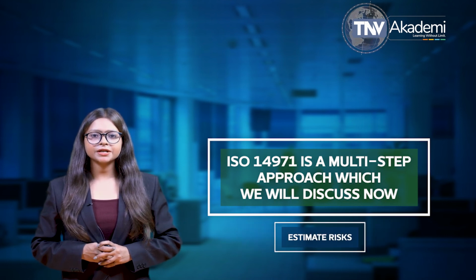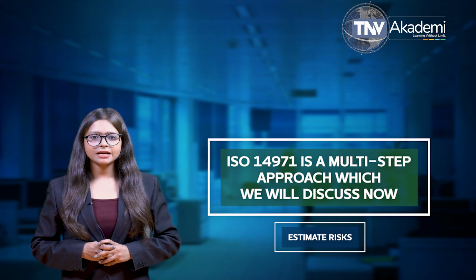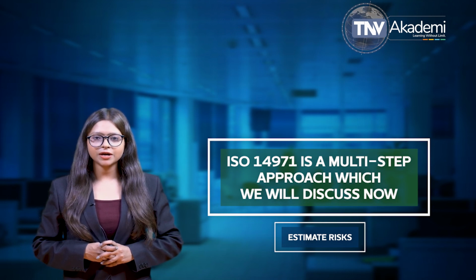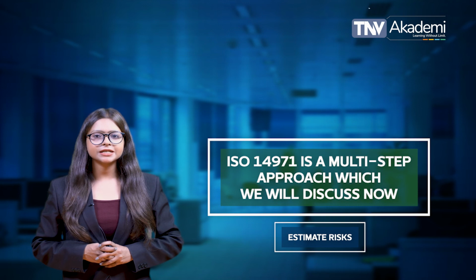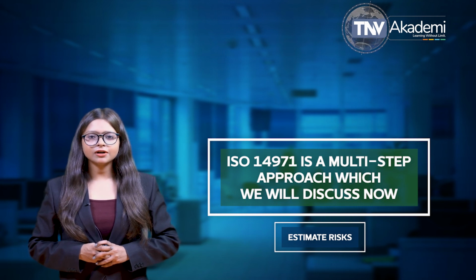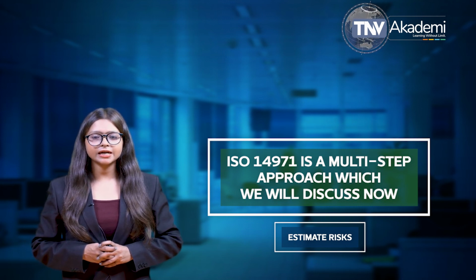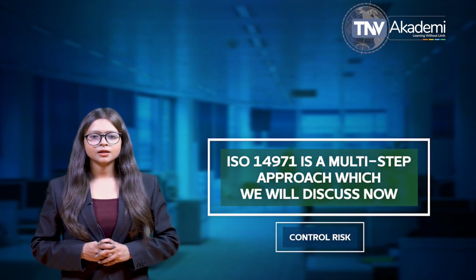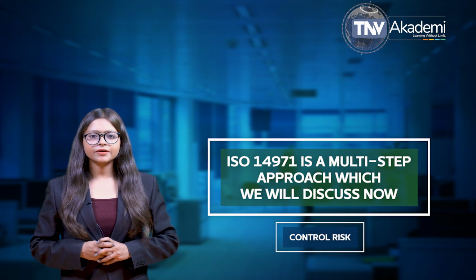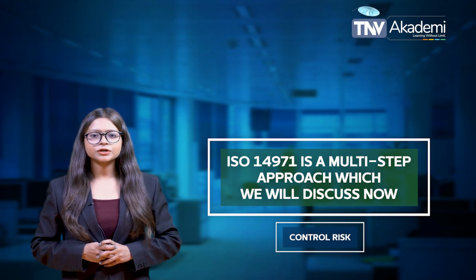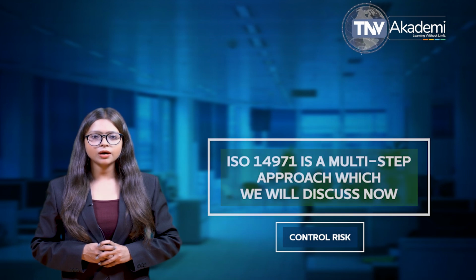Third one is estimate risk. ISO 14971 requires medical device manufacturers to estimate risk by considering all possible negative consequences resulting from the use of their device. There are several ways to identify the risk in medical devices. Then you estimate its probability and impact as defined in the standards. Fourth one is control risk. Determine ways to minimize risk to an acceptable level, which must be clearly communicated to all stakeholders.